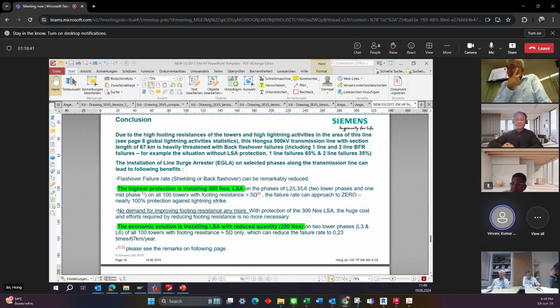In addition to the statistical analysis, we can also provide a specific magnitude of the lightning current, and we can also add the waveform of it. As per the standard from the IEC, there is also a high current value of 100 kiloamps with a waveform of 4 by 10 microseconds. So we can give an input with this magnitude and waveform, and get the results on how much impact it has on the specific transmission tower.